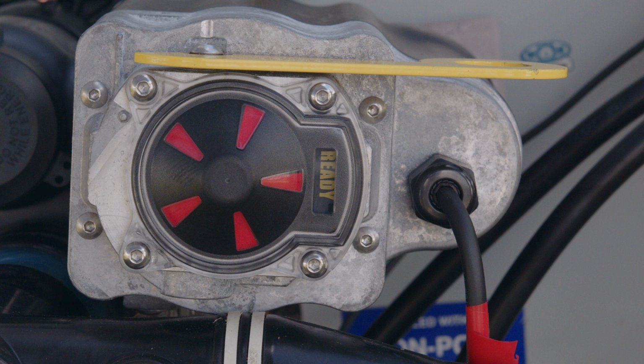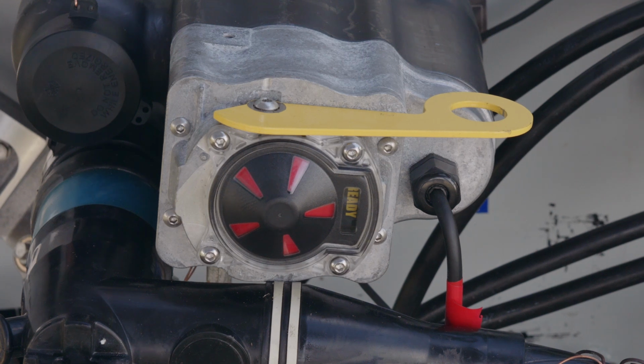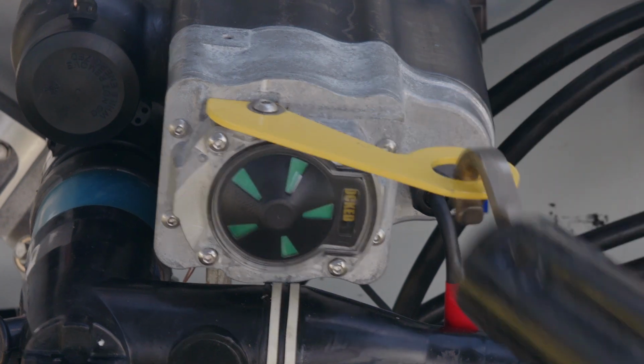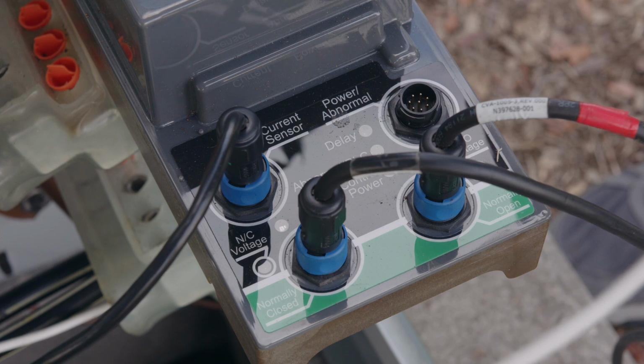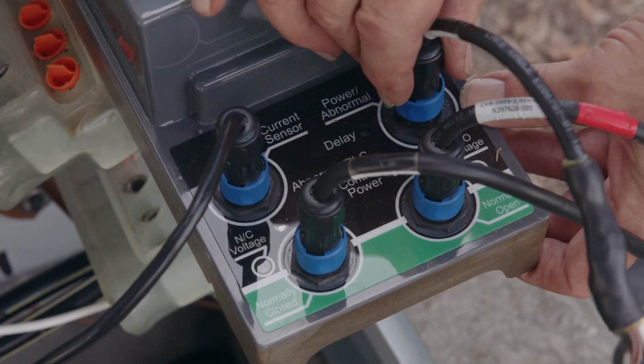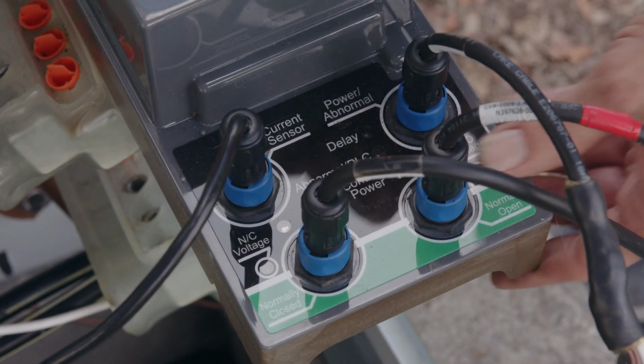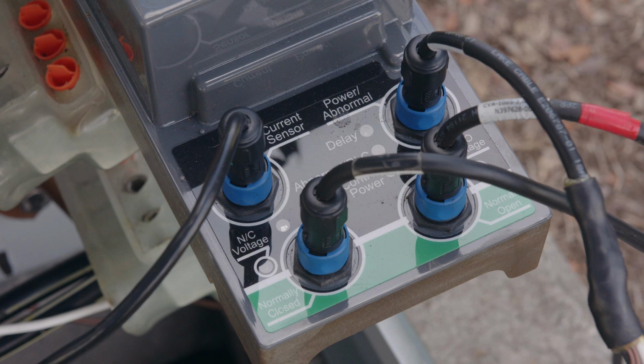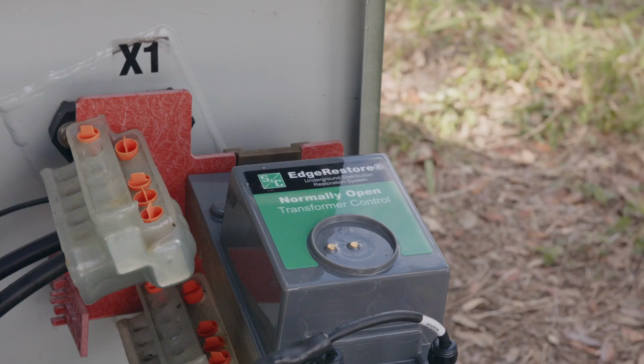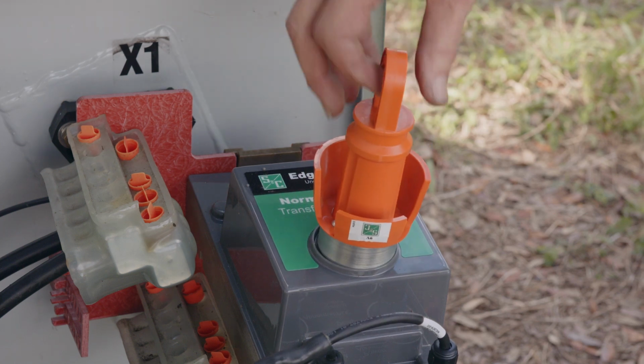The EdgeRestore bushing well interrupters are shipped in the closed position. If utility practice prefers they be installed in the open position, they can be opened by pulling the bushing well interrupter's yellow lever. Note: the bushing well interrupters can only be closed again when control power is applied to the control after energization or before energization by using the cordless power module to supply power to the control.